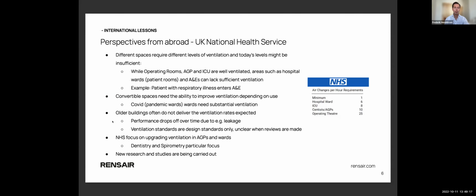The first takeaway is probably not too surprising, but I want to mention it anyway: different spaces, of course, require different ventilation, and today's levels might be insufficient. When you look at operating rooms or AGP spaces, etc., by all means, that is where the focus has been on air quality, and those standards tend to be sufficient, assuming that the amount of ventilation that you expect to be delivered there is in fact delivered.